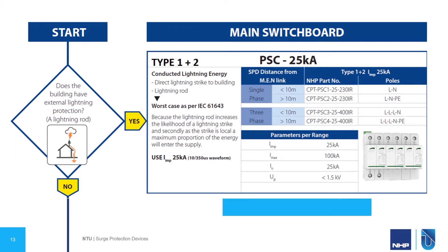So let's move on and take a look at our selection guide. We're going to start by looking at the main switchboard, as this will be the point of entry of supply. Firstly, does the building have external lightning protection, i.e. a lightning rod? If it does, this is seen by IEC 61643 as the worst-case scenario, because the lightning rod not only increases the likelihood of a lightning strike, but it also means that the energy dissipated by that lightning will be very close to our installation. In this case, the standard recommends a Type 1 plus 2 device with a lightning impulse current of 25 kA. Here, NHP recommends using the PSC 25 kA range.